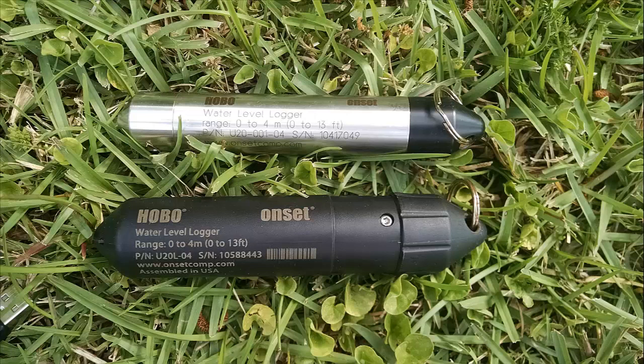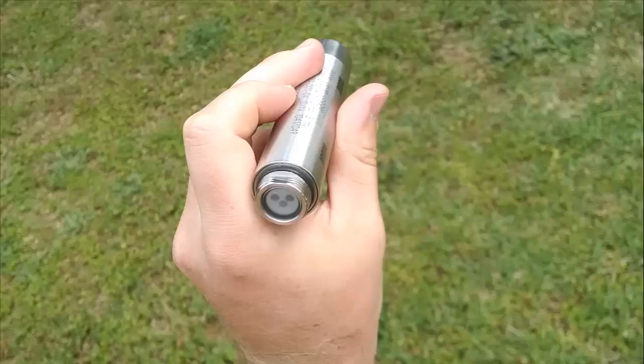Each of these has a removable end cap with a ring in it used to attach it to a cable for deploying down a well. You also remove the end cap to communicate between the logger and computer for setting up and reading out data from the instrument. Here's one of the U20 water level loggers with the end cap removed so you can see the fiber optic communication terminals.